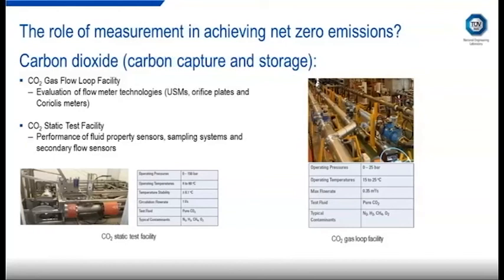We also have a static CO2 facility, which is used for testing the performance of fluid property sensors and sampling systems. It's not a flow measurement facility, and we can circulate the CO2 and the mixtures, but the focus is not on testing flow meters exactly. And this facility can operate at pressures of up to 150 bar across a wide temperature range. So it can work across the full CO2 phase envelope, which is very impressive.